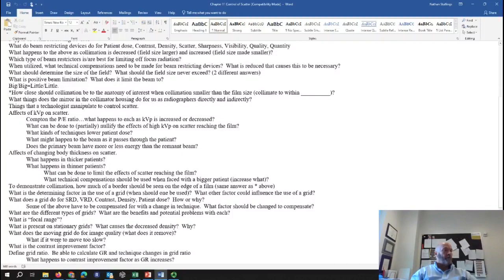With a stationary grid, you may potentially see grid strips — the lead strips on end look like radiopaque stripes. If you use a high-frequency grid, you're less likely to see them because they're very small. Decreased density in that area occurs because the absorber is completely blocking even the good x-rays. A moving grid is used in x-ray tables — the purpose is to blur out grid lines, similar to a breathing technique blurring out lung markings.